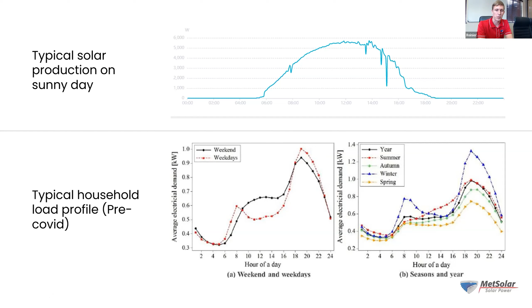I have two examples of a residential installation, one without load optimization and one with load optimization. If you follow the top graph, the blue line is your solar production. This house doesn't have high loads during the day except around peak time, and it charges the battery full by 9 a.m., so solar production drops off to match the load. You're not getting the maximum out of the system - it only generated 11.6 kilowatt hours for that day.